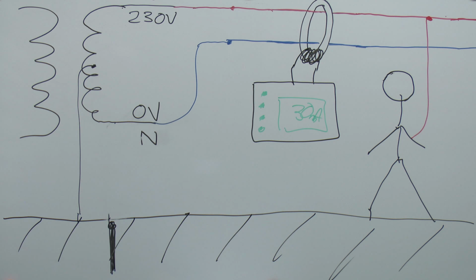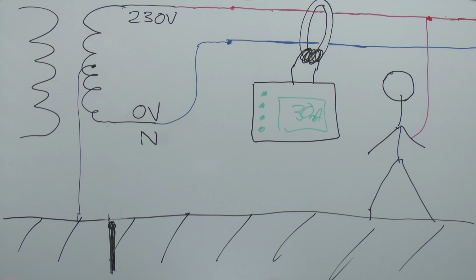The idea being that if some fault occurs where the current then increases beyond a predefined limit, rather than disconnecting the whole building and causing massive inconvenience, it will just sound an alarm, and therefore the problem can be investigated and repaired when it's more convenient. Obviously you wouldn't want an entire data center full of thousands of computers just being suddenly turned off because some minor piffling fault occurred somewhere in the building.